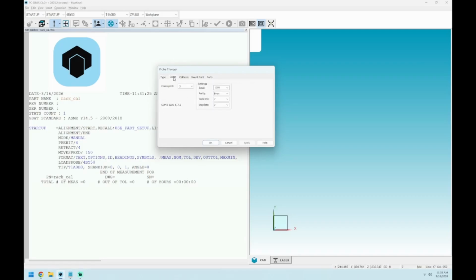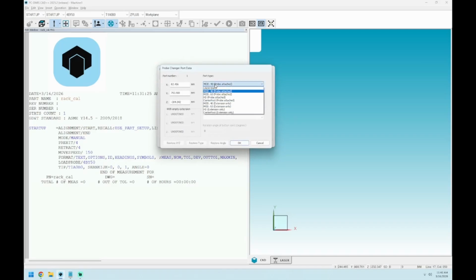The next part is the Communications Port tab. All of this information should be up to date and installed by the service team, so please reference the service manual if you ever need to change anything in it. The mount point is where the probe will move to and from before and after it docks or undocks from the rack. It is also where the probe will rotate after a new docking, so you want to make sure it is clear of the rack.